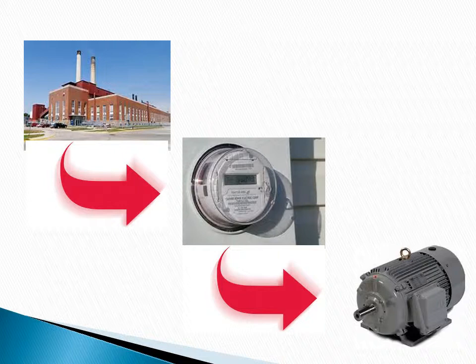What is reactive power? Reactive power is the power that comes from your utility company through your meter to the windings of your motors to create the electromagnetic field so the motors will turn. The wasteful part of this energy is never consumed. You pay for this wasted amount of energy every day. It creates a magnetic field and then dissipates in the form of heat and line loss. This process repeats itself 60 times a second.